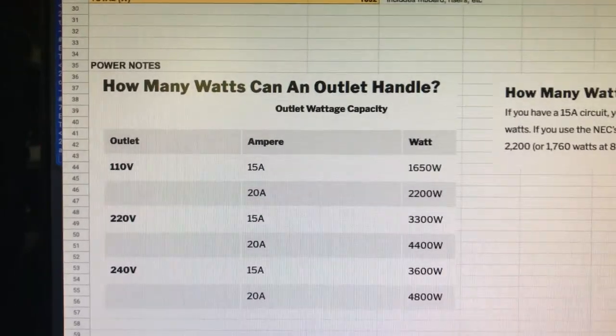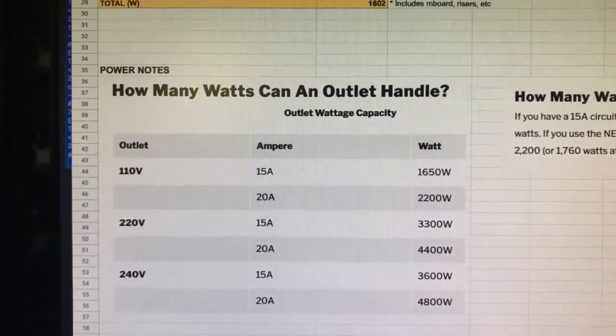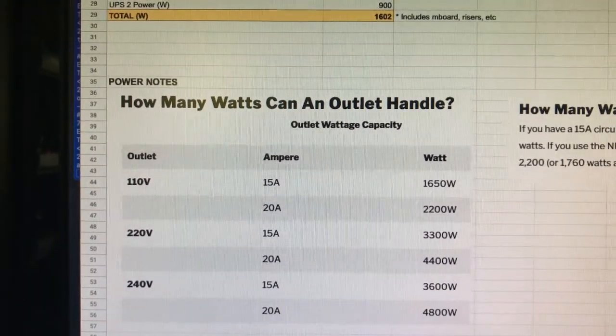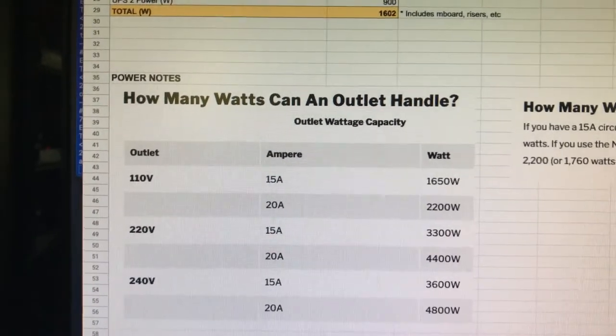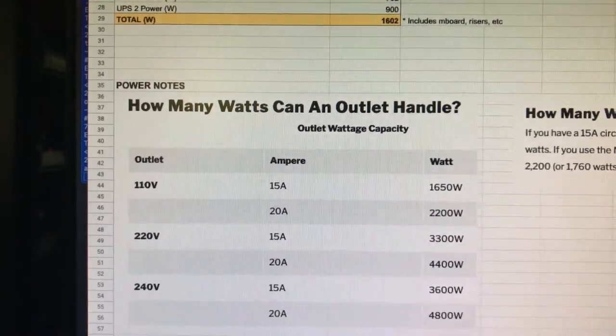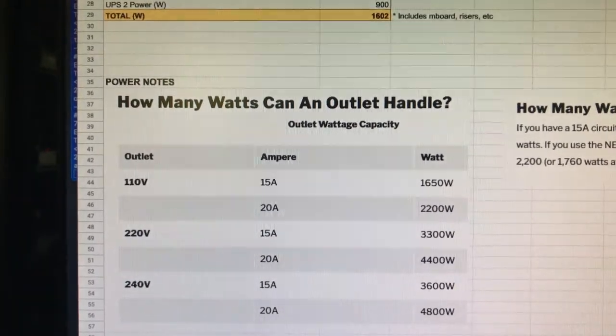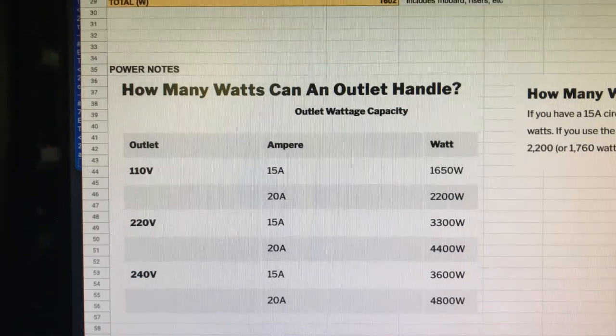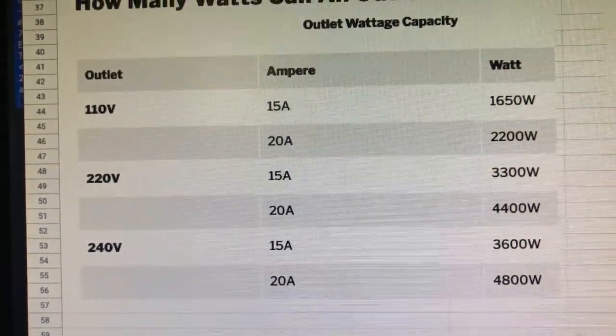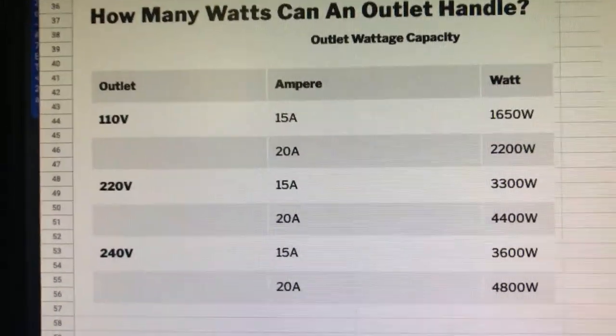With a 20-amp circuit, you have 2,200 watts that you can use. If you use the 80% rule, that gives you a safe 1,760 watts. You can see more values in the table based on your home setup. In the US, typically it's 110 volts, 15 amp.